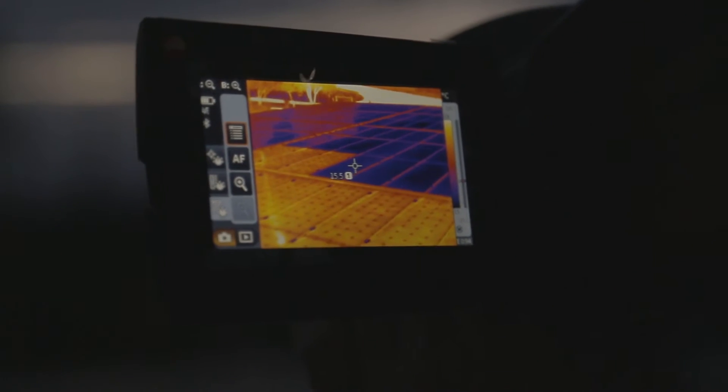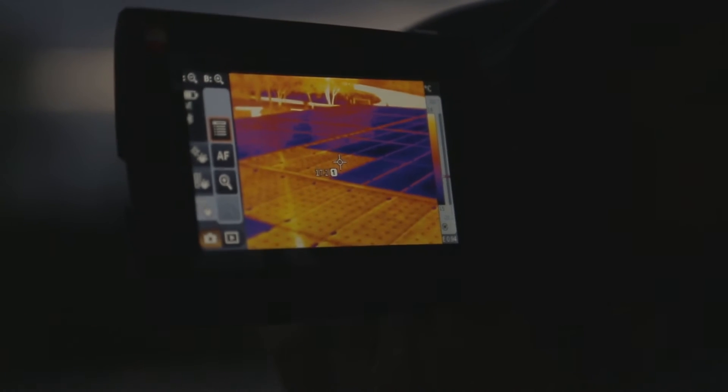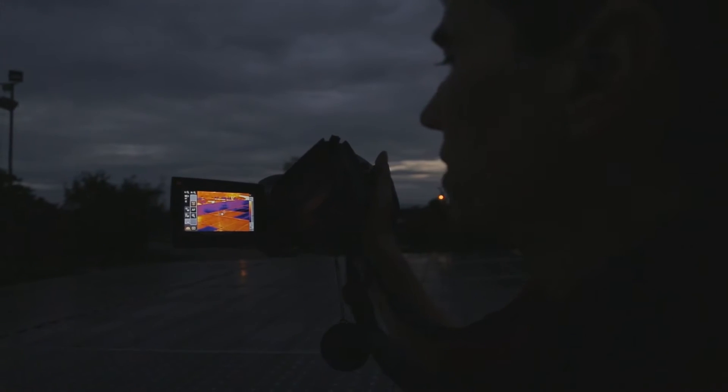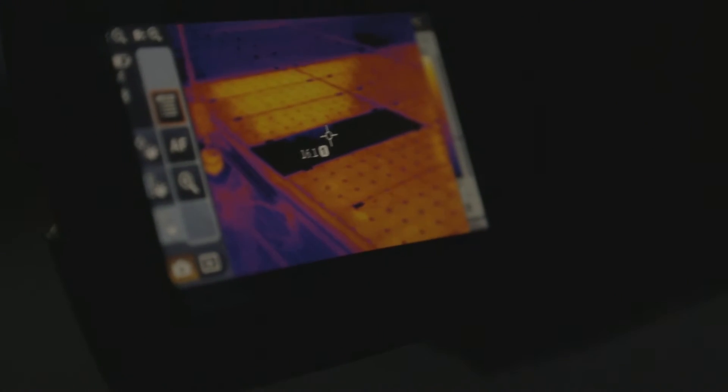So let's send current back through the panels. We can easily see here that some areas are much cooler, though strings in the back do not have current running backwards through them. In contrast, the front string has current running backwards through it, and it's warm. You can clearly see where the individual panels are. You can also clearly see that this string under investigation has a defective panel.